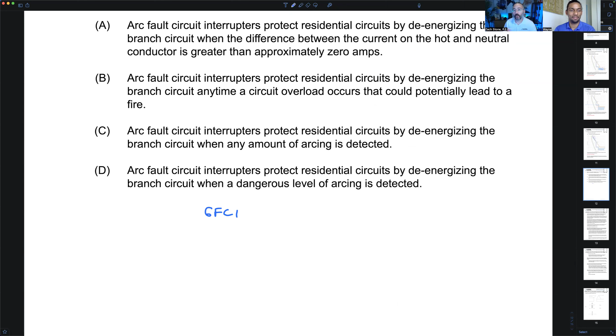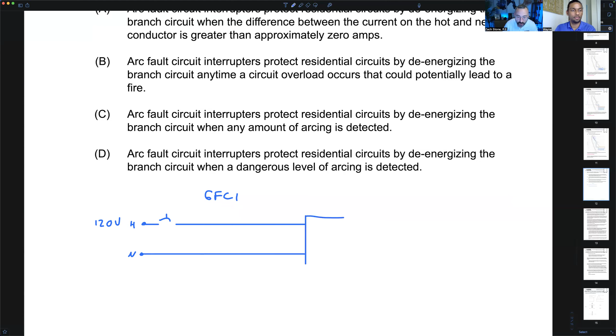Anytime you see the test or reset button, maybe the wife's trying to use a hair dryer, she's complaining it's not working, you just got to hit the reset button. Or there are also GFCI breakers that you can use as well. The way these devices work, here's our single pole breaker coming out of the panel, 120 volts. Here's our hot coming off the breaker. Here's our neutral return. And here's our receptacle. Something like this.